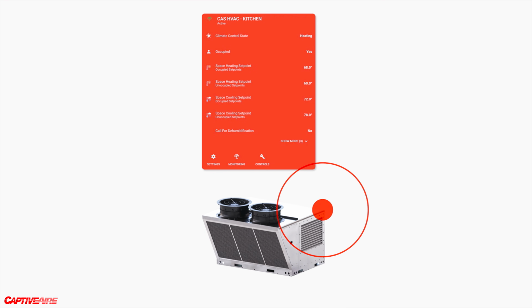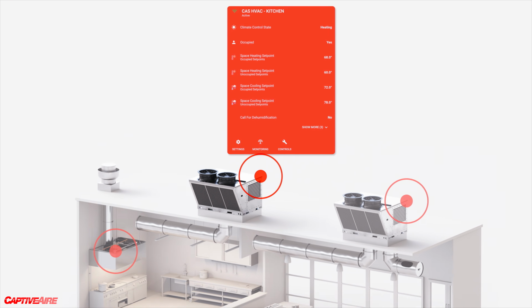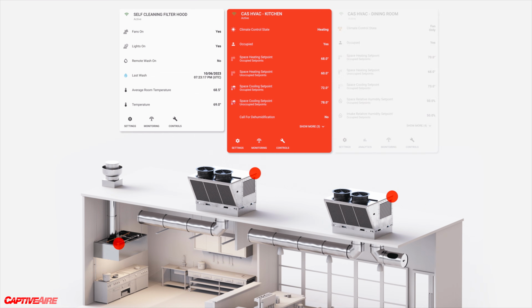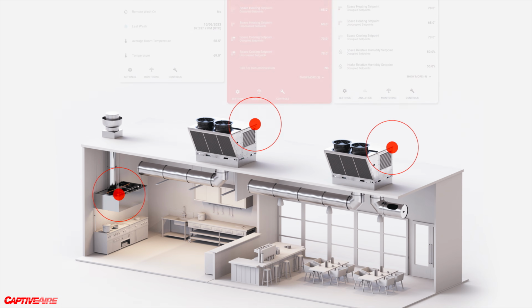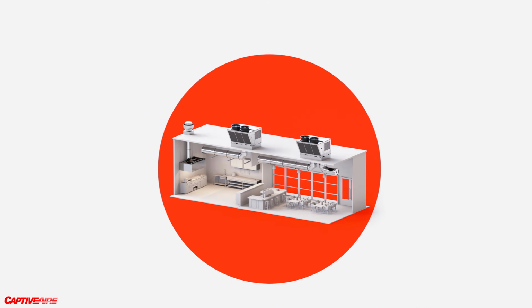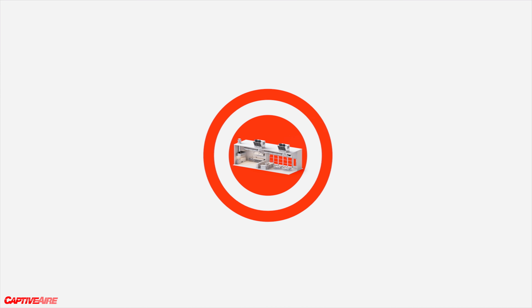At the smallest level, we could view our one piece of equipment. We can verify the unit's doing what we expected, but we have so many other pieces of equipment operating in that same facility that we also want to tie them all back into CASLink and see, as a whole, what this building is doing. Because even if our one component's working right, if another component's doing something we weren't expecting, it can have an impact on that initial component.